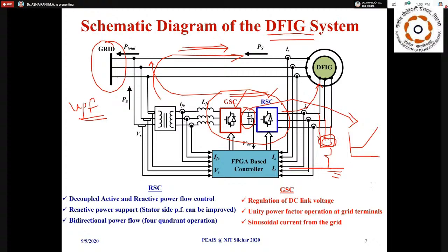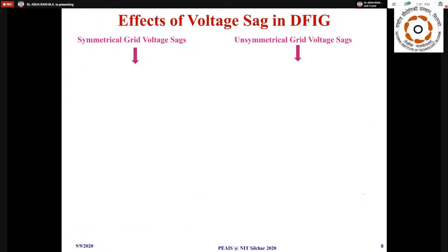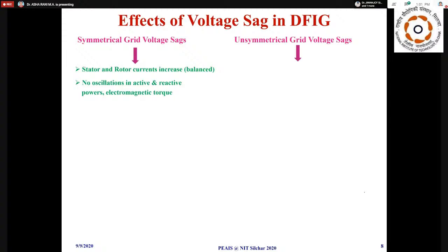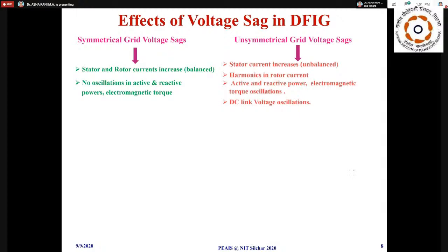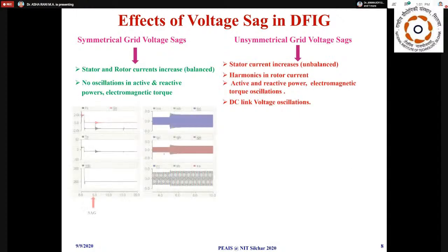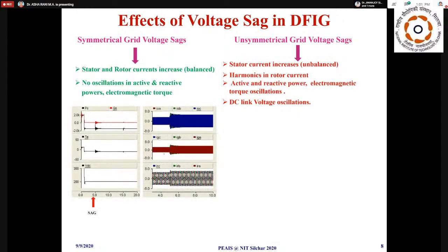And if you continue like that for some time, it can create severe issues for the grid also. So what are the effects of voltage sag in DFIG? Basically, we know voltage sags, or what we call unbalance, are symmetrical and unsymmetrical in nature. So let us see what happens with symmetrical grids. If it is symmetrical, the stator and rotor currents will increase.